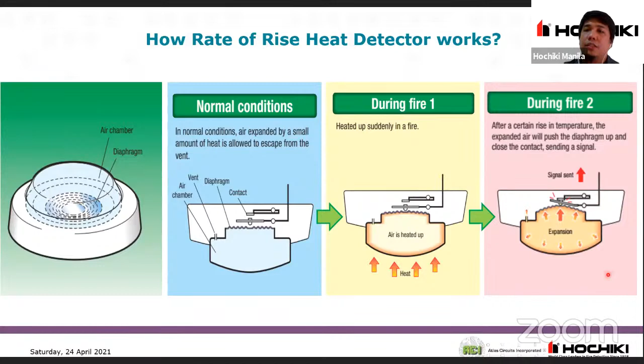When there's heat, there's still venting happening. Once it satisfies the condition, which is 15 degrees in less than 1 minute, the diaphragm will expand, causing the contacts to activate. Once the contacts activate, it will give a signal to our panel.